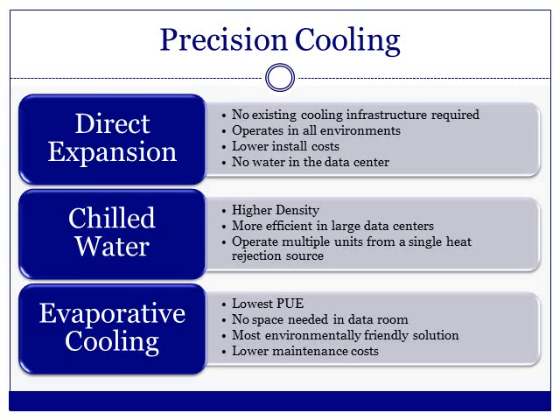When it comes to cooling a data center, there are three prevalent approaches: direct expansion cooling, chilled water cooling, and evaporative cooling. In order to select the best overall heat rejection method, site conditions and sometimes customer preferences must be considered when designing an efficient, cost-effective solution. Direct expansion cooling is a popular choice in precision cooling because it does not require any existing cooling infrastructure to be present to be installed, for example, a chilled water loop.